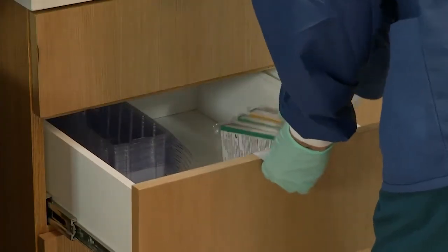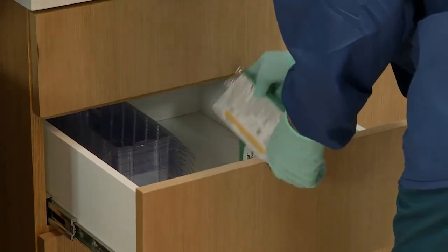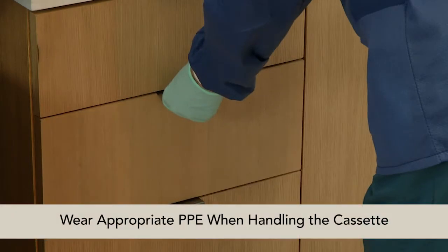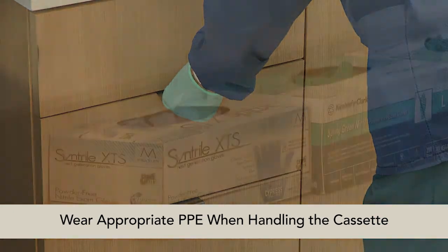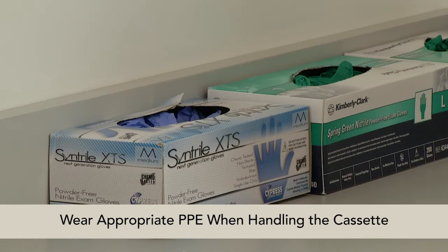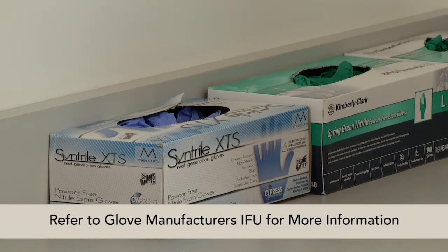First, take a new STERAD NX cassette out of the shipping carton. As a precaution, when handling any part of the system or load items that have been exposed to hydrogen peroxide, please wear the appropriate PPE, specifically chemical-resistant latex, PVC vinyl, or nitrile gloves. Refer to the glove manufacturer's instructions for use for more information.